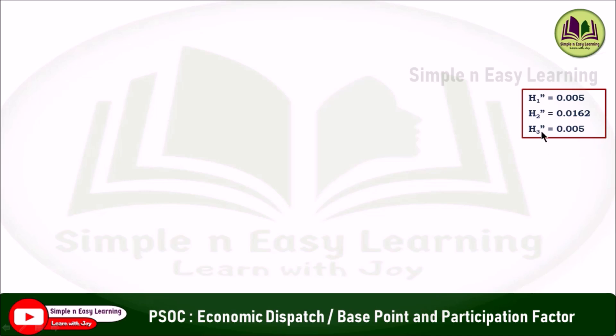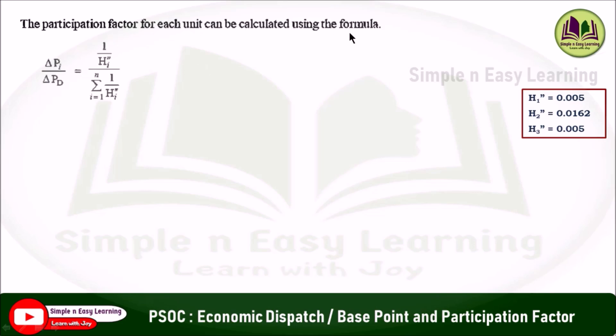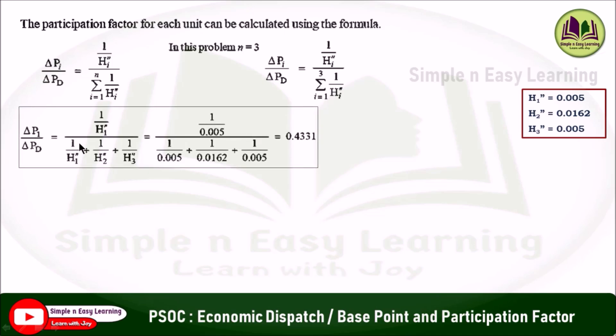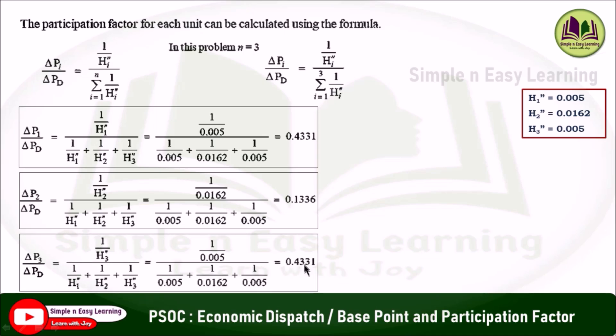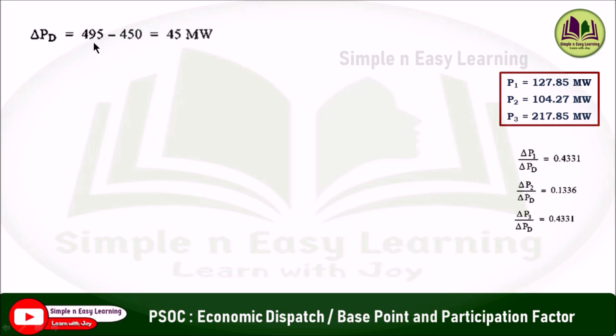Now use these values to find the economic schedule using the base point and participation factor method. The participation factor for each unit is: ΔP_i / ΔP_d = (1/h_i'') / Σ(1/h_i''), where n = 3. Substituting all values: ΔP1/ΔP_d = 0.4331, ΔP2/ΔP_d = 0.1336, ΔP3/ΔP_d = 0.4331. The change in demand ΔP_d = 495 − 450 = 45 megawatt.